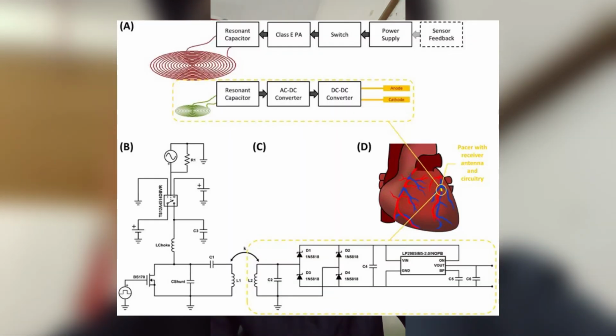This not only helps maintain the function of the implant but also protects the patient from potential harm due to malfunction. The core concept behind these protective circuits is high voltage suppression. This is often implemented using Zener diodes, which are designed to remain non-conductive under normal voltage conditions but begin to conduct current in reverse when a specific Zener voltage is exceeded. For instance, a 5.1 volt Zener diode will block voltage until it rises slightly above 5.1 volts, at which point it clamps the voltage and prevents it from increasing further. This makes it extremely effective for limiting transient voltages caused by sudden surges.